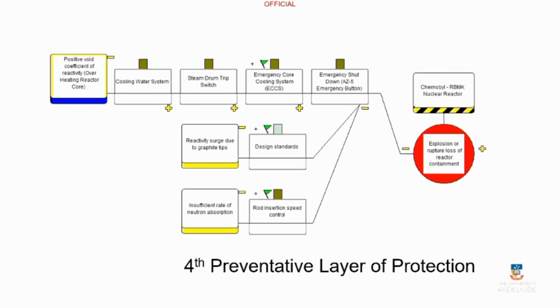That acted as an absorber, which slowed the reaction down. As soon as they pressed the AZ button, as the control rods were being inserted, they pushed out the water, which was acting as an absorber, creating a sudden surge of reactivity, which then created a high amount of steam generation, positive void coefficient occurring, overheating, and then the incident.